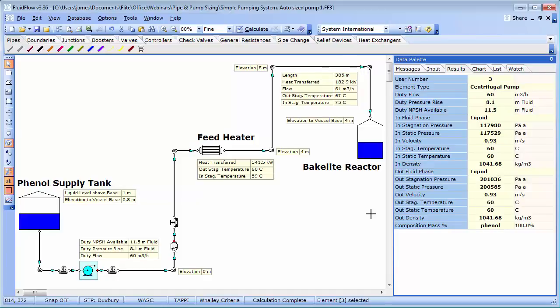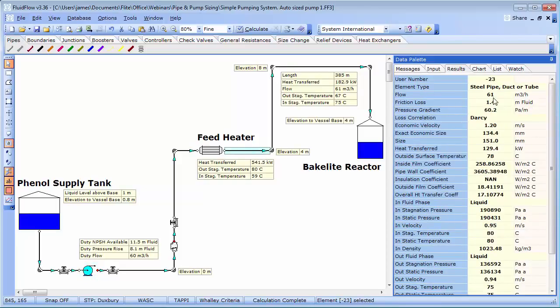Before we fill out our pump datasheet and contact our pump supplier, there are other considerations we should make such as, is the net positive suction head available a sufficient margin? The volumetric flow rate after the heater increases. Will this impact on my system design? Start up and shut down. Do we need to drain the line as phenol solidifies at 40 degrees C? Should we steam trace or heat the line? Do we need any relief devices?